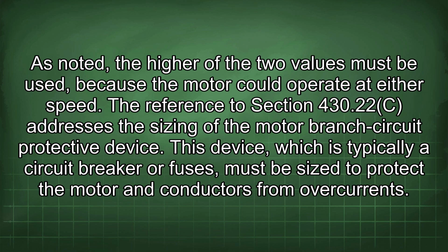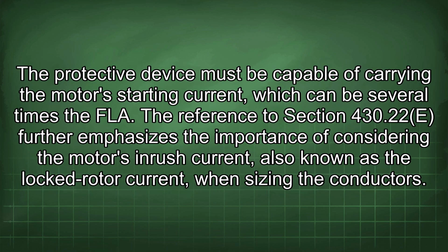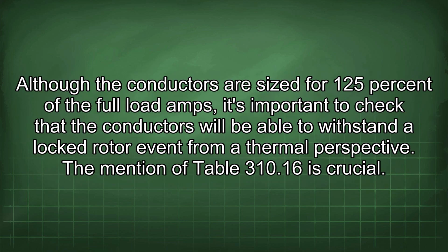The reference to section 430.22c addresses the sizing of the motor branch circuit protective device. This device, which is typically a circuit breaker or fuses, must be sized to protect the motor and conductors from overcurrents. The protective device must be capable of carrying the motor's starting current, which can be several times the FLA. The reference to section 430.22e further emphasizes the importance of considering the motor's inrush current, also known as the locked rotor current, when sizing the conductors. Although the conductors are sized for 125% of the full load amps, it's important to check that the conductors will be able to withstand a locked rotor event from a thermal perspective.